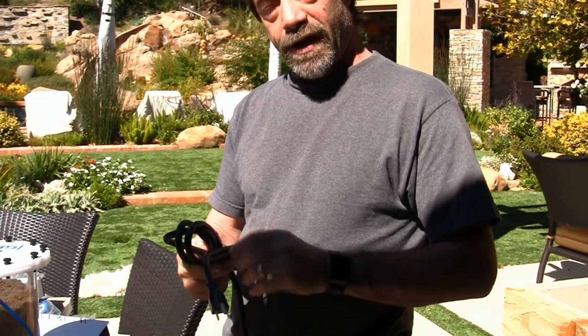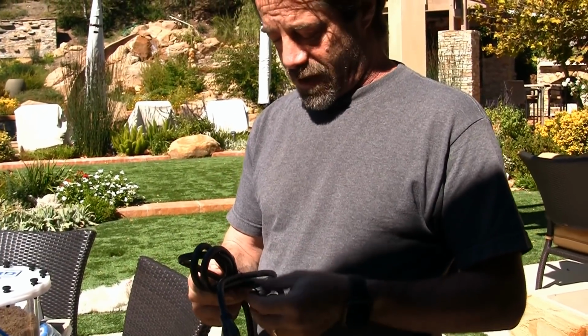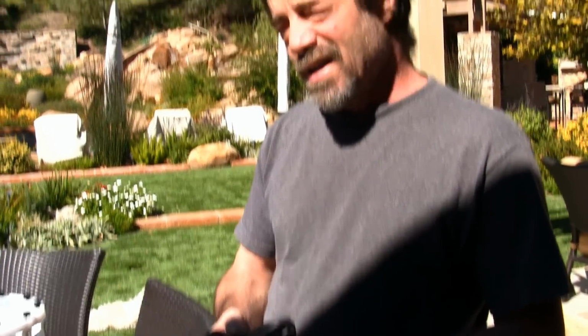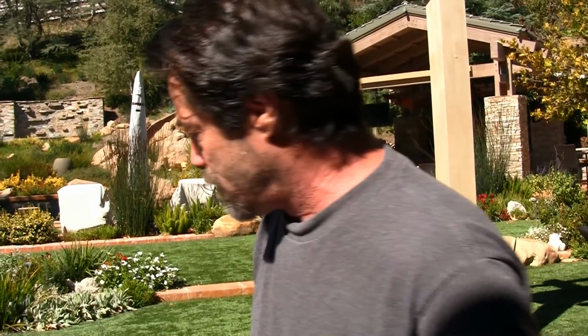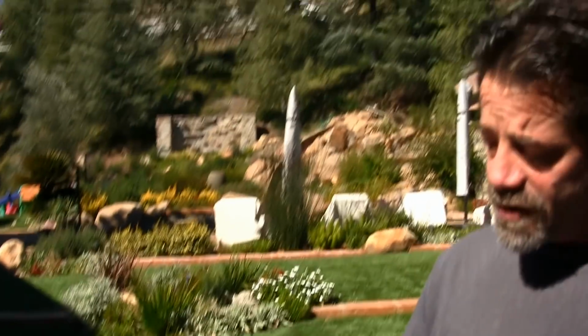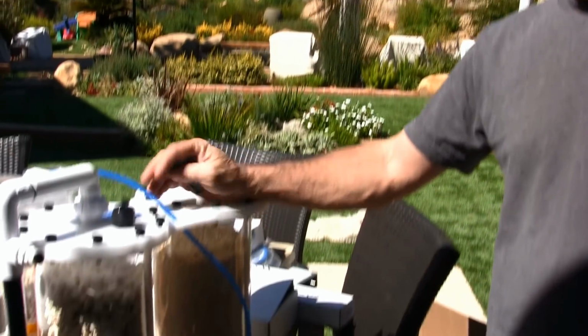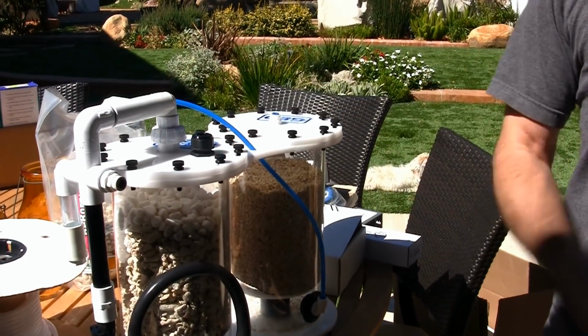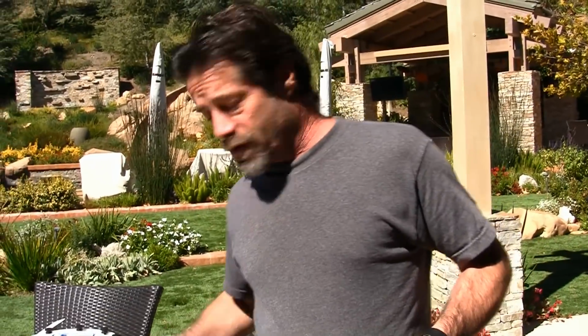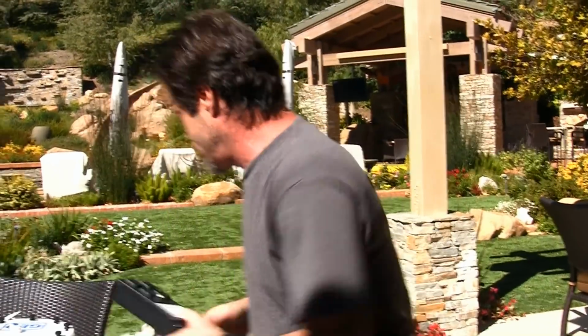We want to make sure that the water maintains a low pH level so that it's acidic. We're going to target a range of around 6.6 to 6.7 in the reactor, and then we'll just manage the flow through the reactor in order to keep up with the tank's alkalinity needs. So first things first, get some stuff in here mounted up.